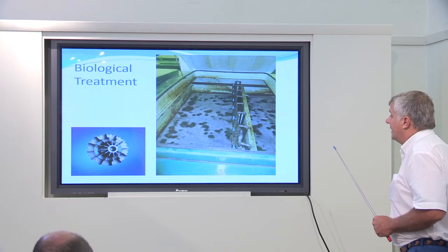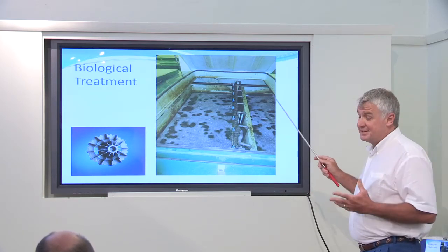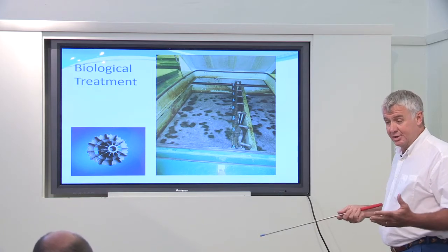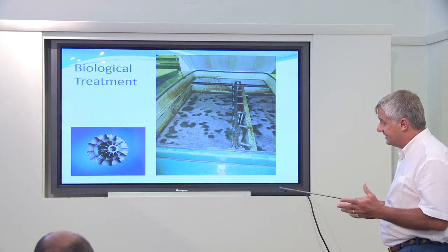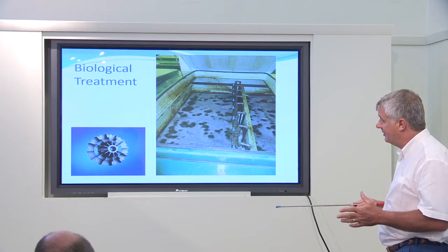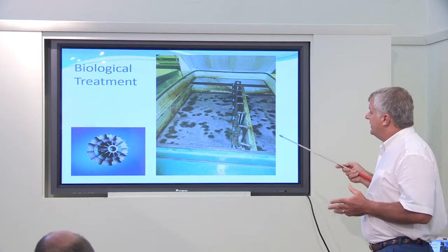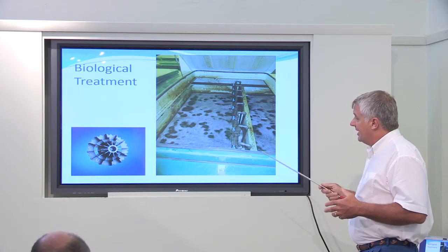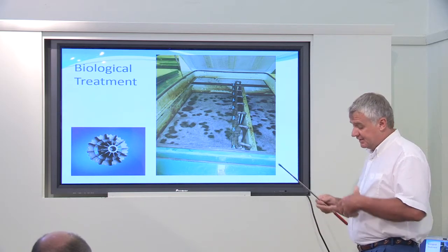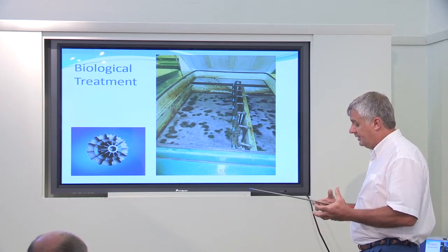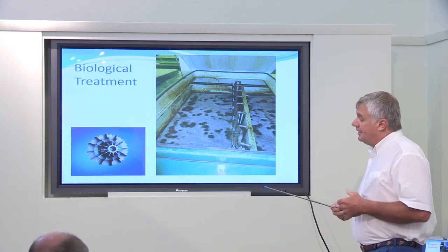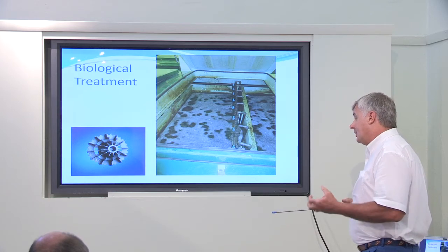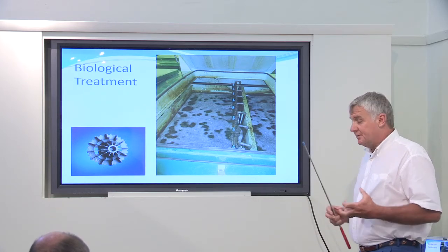The next one shows you a little bit about what happens inside of these tanks. A lot of that bacteria requires oxygen, like a lot of living things do. Some doesn't require it. There's anaerobic bacteria that works without oxygen. But in order to provide that environment, there are a series of compressors that blow lots and lots of air into these tanks and keep everything moving around and oxygenated. And the bacteria, in order to work properly and break down the organic matter, requires lots and lots of surface area in there.